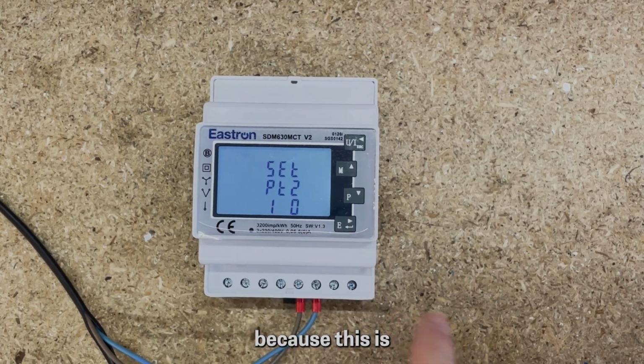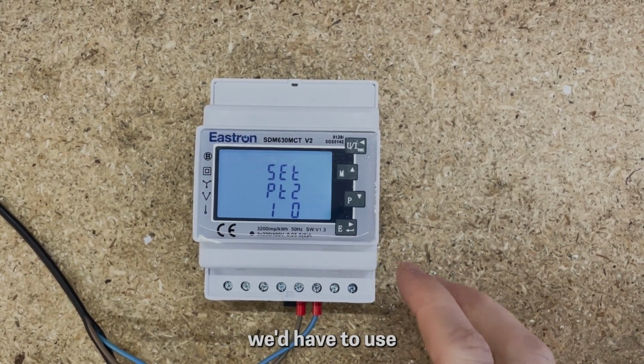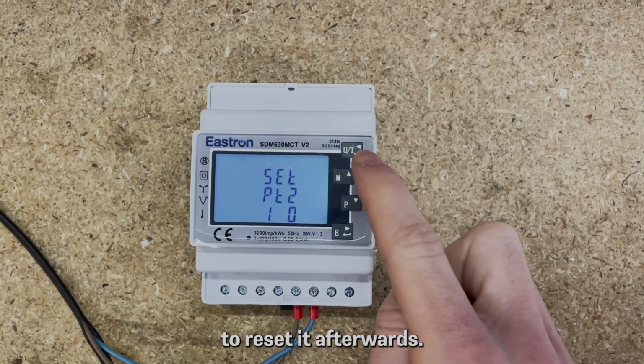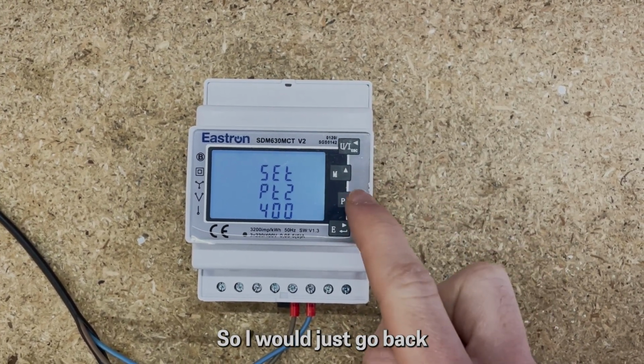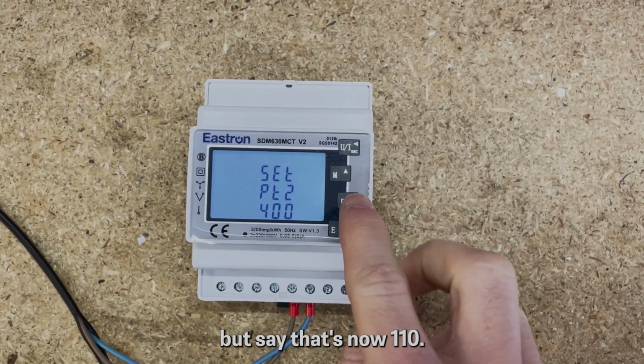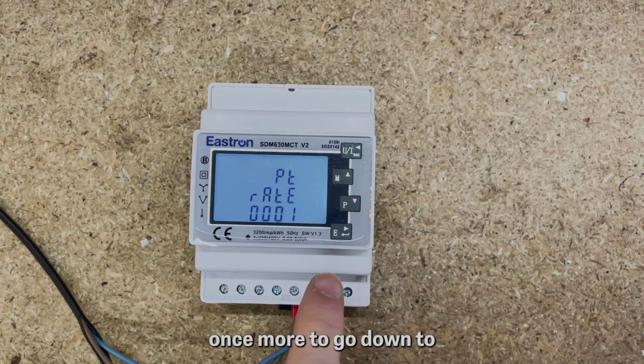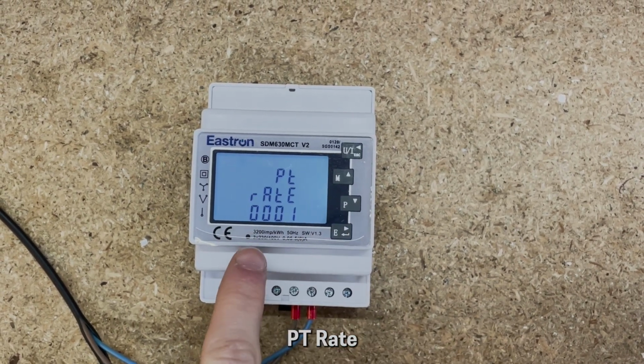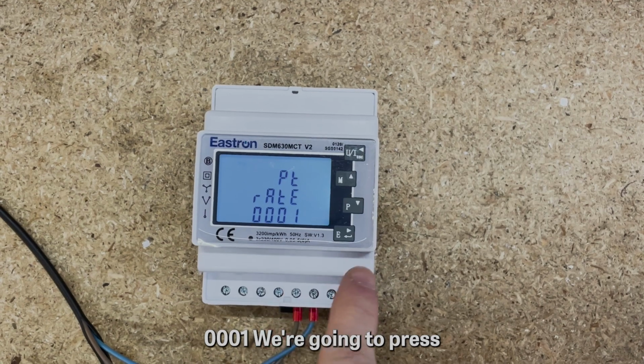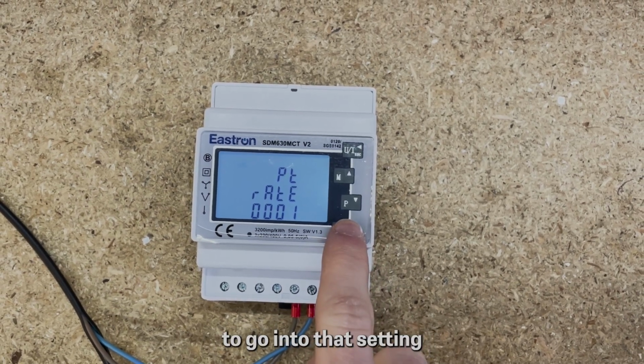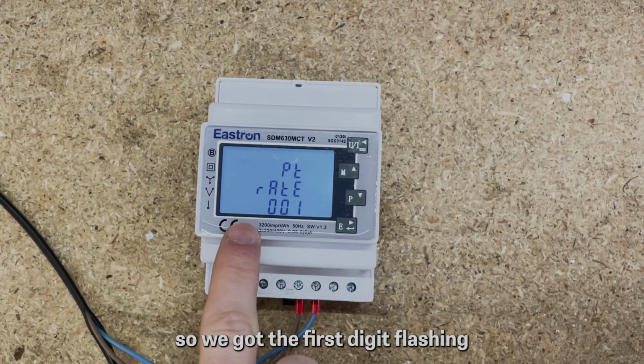I'm not going to do it because this is an MID approved meter, and it means we'd have to use a reset code to reset it afterwards. So we'll just go back. But say that's now 110. Then we press the P button once more to go down to PT rate 0001. We're going to press and hold E to go into that setting. So we've got the first digit flashing.